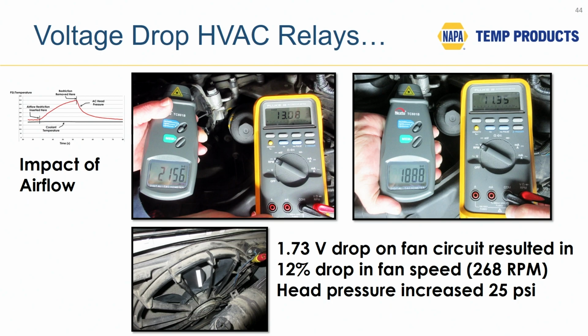Same thing goes for cooling fans. In this particular example, I'm using an infrared tachometer to measure the cooling fan speed. You can see the little white strip on the back of the fan blade. A 1.7 volt drop on the cooling fan circuit resulted in a 12% drop in fan speed. It dropped by 268 RPM, and high side pressure went up by 25 PSI. Again, a simple voltage drop check at the cooling fan would have picked up that it wasn't getting enough voltage.